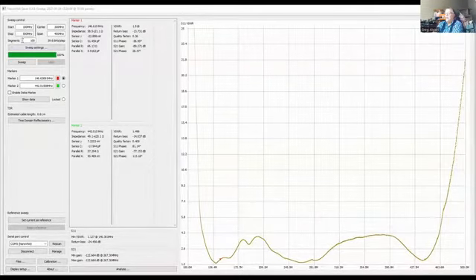But what this software allows you to do is to put in segments. In every segment, it uses the analyzer and gathers those 1,001 points, and it breaks this whole start and stop range up into, in this case, 100 segments. So you get a lot more resolution and a lot better measurement by doing that. Okay, I'm going to stop sharing that screen, and we'll go back to the PowerPoint.